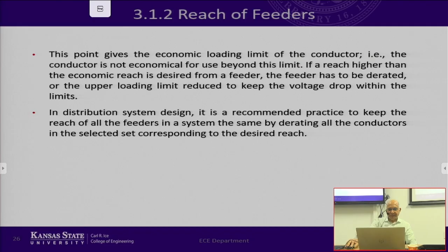So then we find those values and draw a new graph for conductor number 1, number 2, number 3, and number 4. This graph shows the 4 conductors with the cost associated with the reach, because instead of the intersection between conductors happening at the economic point, the reach has now become a factor too. So the curve doesn't go all the way to the intersection point; it jumps before that. The graph becomes modified based on these calculations, giving us the modified cost characteristics for the conductors while accounting for the reach we're interested in.